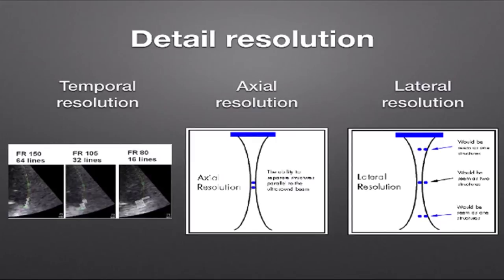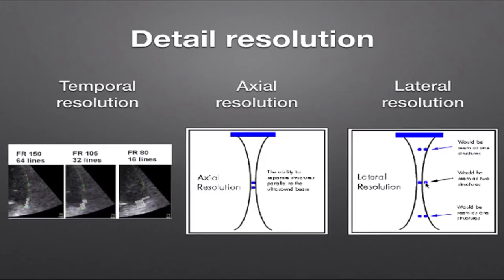The focal zone is critical for lateral resolution. Trying to differentiate two structures in the near field or far field will make them appear as one, whereas in the focal zone the lateral beam thickness is narrowest, allowing two structures to be displayed as separate points. It's important to remember that axial resolution is always better than lateral resolution.